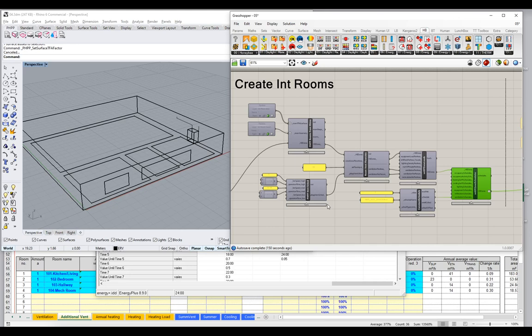So what did we do? We calculated our flow rates based on the user input. So rather than the Energy Plus schedule, we gave explicit room-by-room flow rate information. We calculated the equivalent ventilation flow rates. We overrode the standard Energy Plus loads for ventilation. And then we overrode the variable schedule with a constant schedule so that it more closely matched the way the PHPP is working.